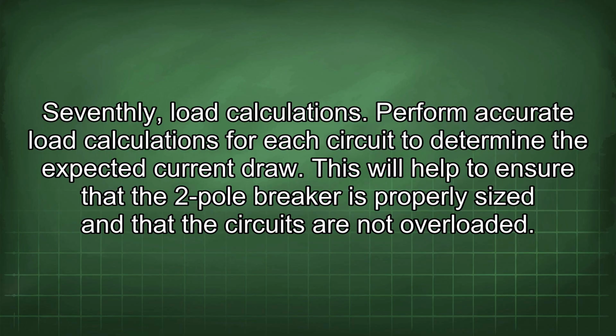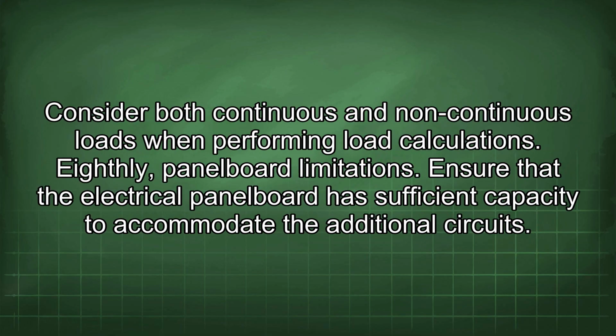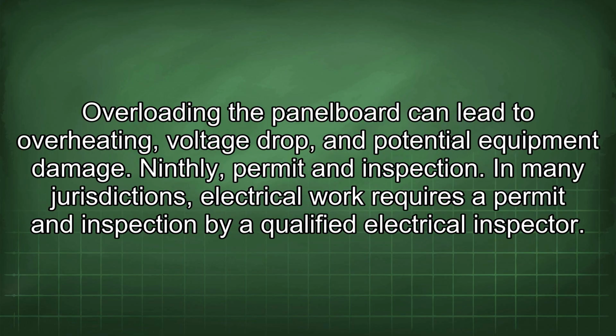Seventhly, load calculations. Perform accurate load calculations for each circuit to determine the expected current draw. This will help to ensure that the two-pole breaker is properly sized and that the circuits are not overloaded. Consider both continuous and non-continuous loads when performing load calculations. Eighthly, panel board limitations. Ensure that the electrical panel board has sufficient capacity to accommodate the additional circuits. Overloading the panel board can lead to overheating, voltage drop, and potential equipment damage.